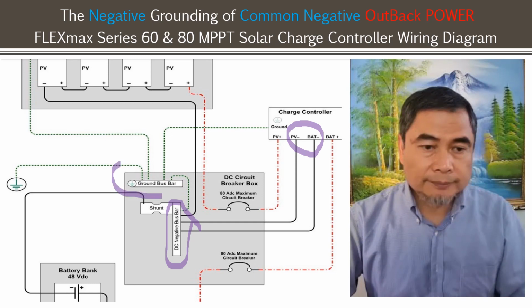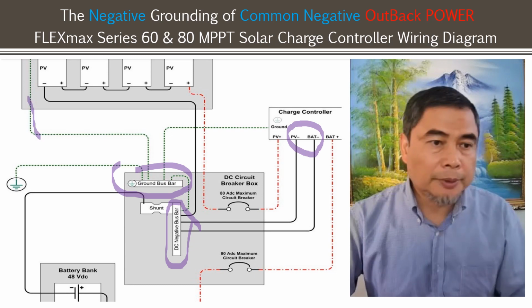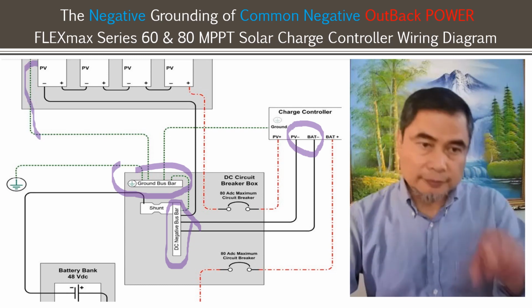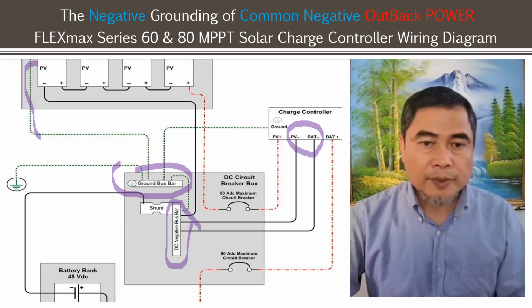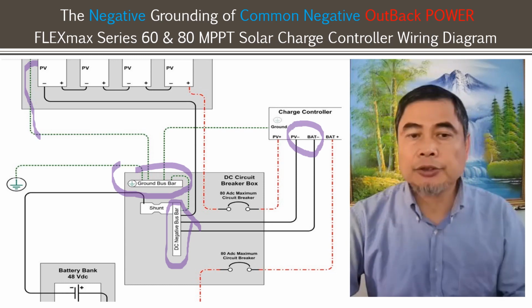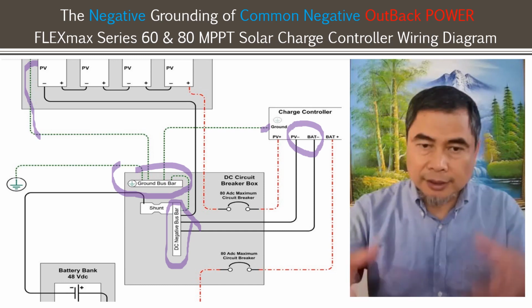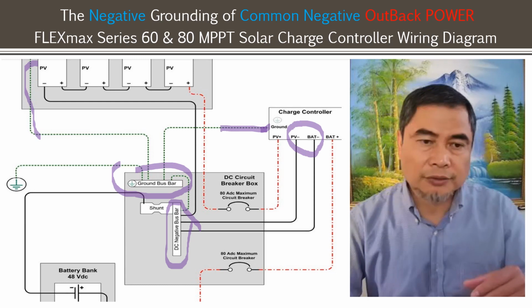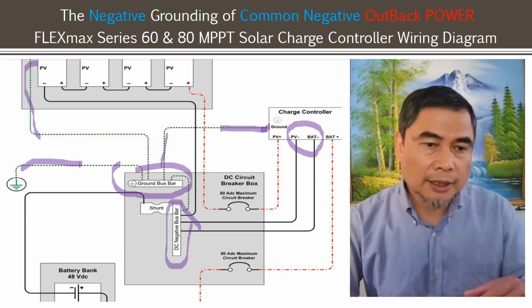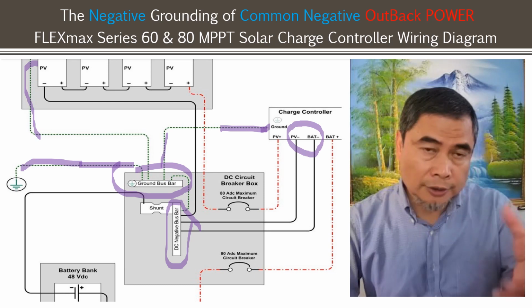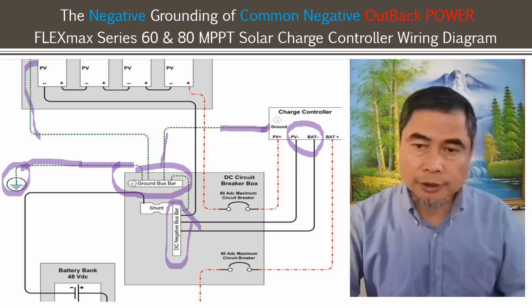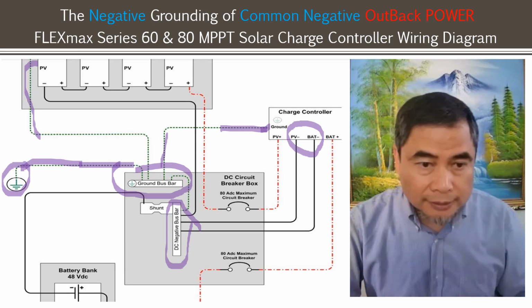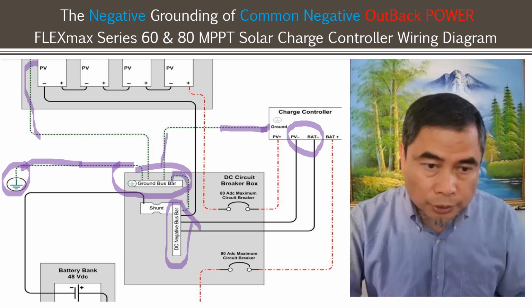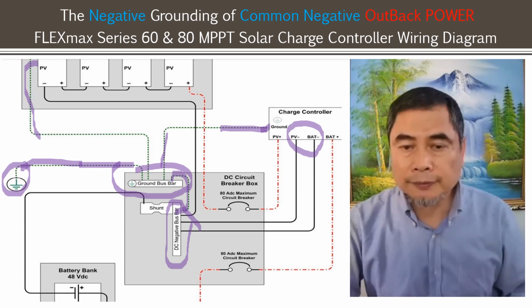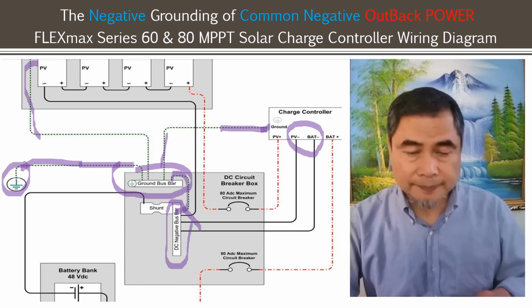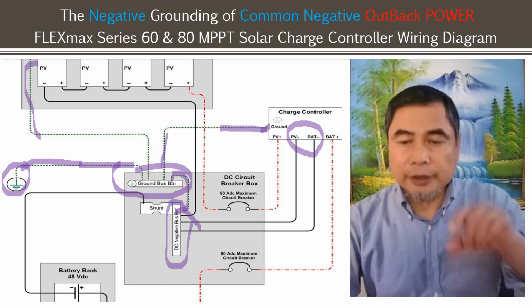The ground bus bar here connects the aluminum frame. This connects all the solar panel frames to the ground bar as well, and this is connected to the MPPT solar charge controller. This casing, which could be a metal casing, is also connected to the ground, and this is a ground cable, minimum gauge number 6, that goes to the approved ground construction. And you see that this ground bar is also connected to the negative terminal of the system, PV negative. So this is a negatively grounded system.